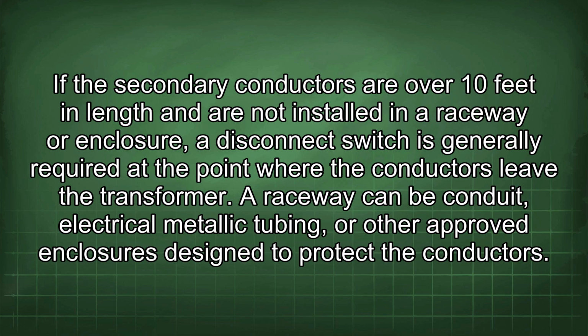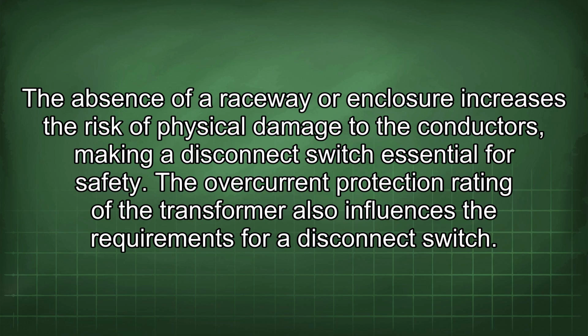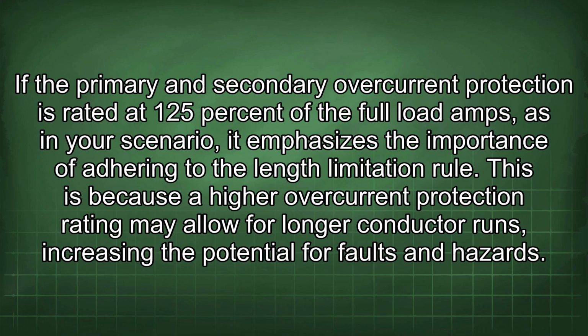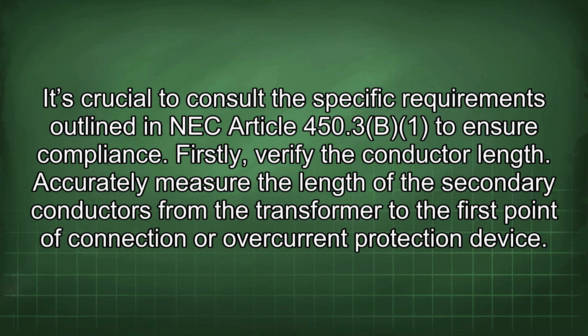A raceway can be conduit, electrical metallic tubing, or other approved enclosures designed to protect the conductors. The absence of a raceway or enclosure increases the risk of physical damage to the conductors, making a disconnect switch essential for safety. The overcurrent protection rating of the transformer also influences the requirements for a disconnect switch. If the primary and secondary overcurrent protection is rated at 125% of the full load amps, as in your scenario, it emphasizes the importance of adhering to the length limitation rule. This is because a higher overcurrent protection rating may allow for longer conductor runs, increasing the potential for faults and hazards. It's crucial to consult the specific requirements outlined in NEC Article 450.3(B) to ensure compliance.